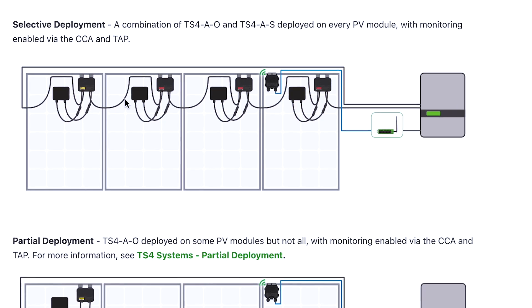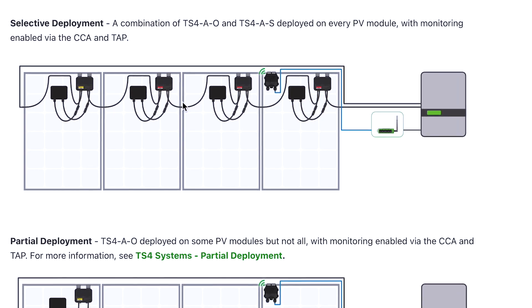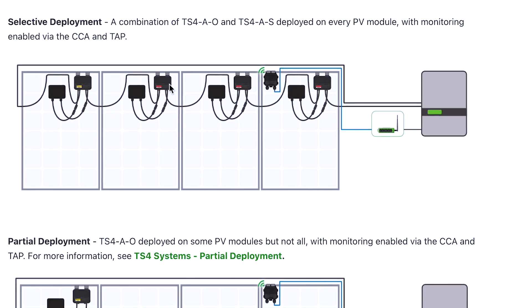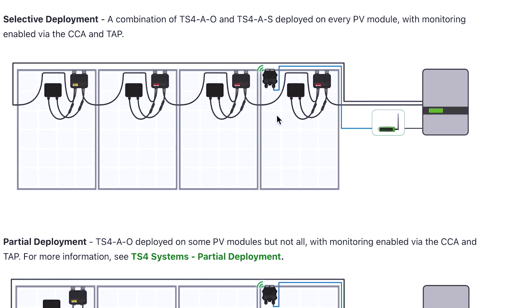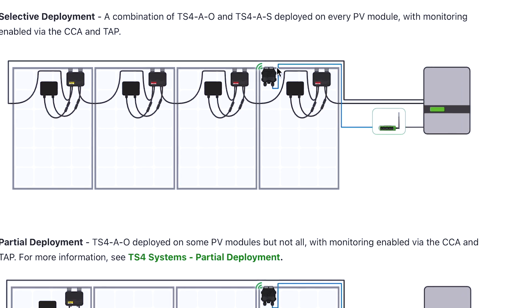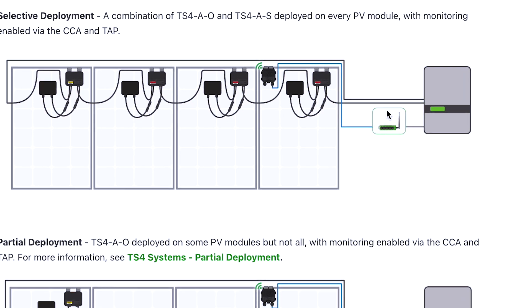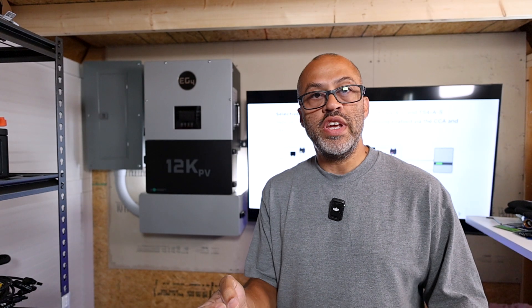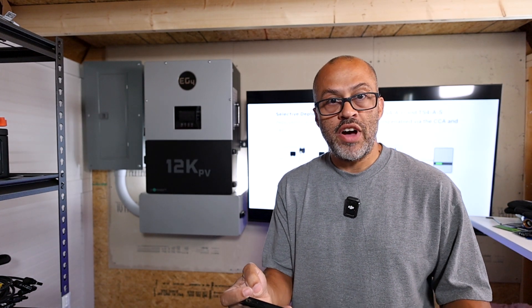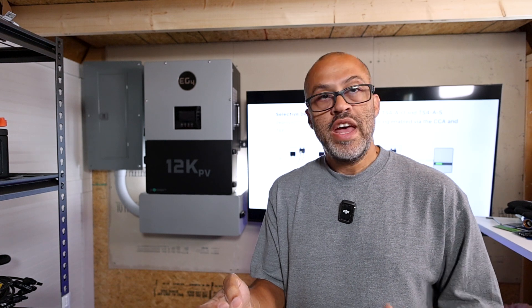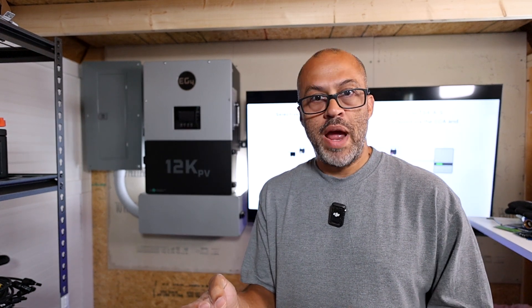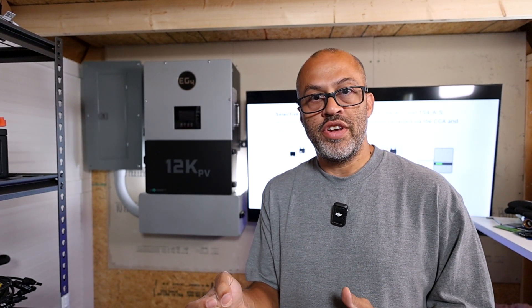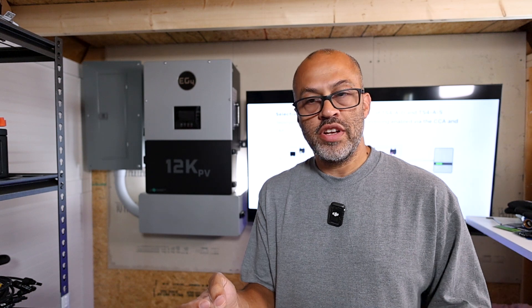Selective deployment is a combination — you have the TS4-AO and a TS4-A-S deployed on every module with monitoring enabled via the CCA or TAP. Maybe some panels need optimization because they're getting shading, and some you just want for rapid shutdown. That would be that scenario and combination.